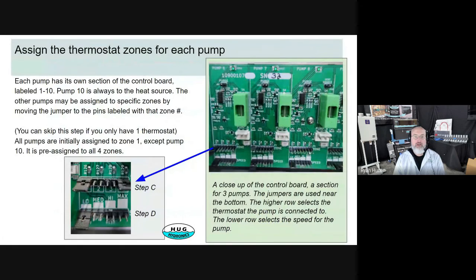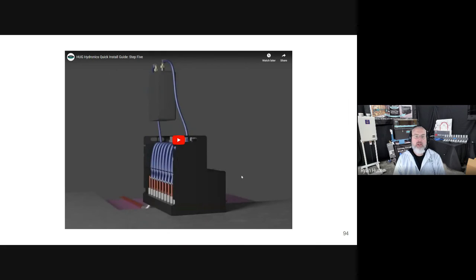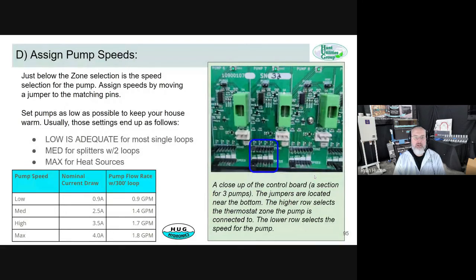All right. So, assign which thermostat controls it and how fast it goes. I've got a pump guide here. That's the table you were looking for. On low speed, it's 0.9 gallons per minute on a single loop. If you ran double loops, it'd be about 0.81 gallons per minute, which is right in the normal range, especially for a concrete floor. For medium, it's 1.4 gallons a minute. It's a pretty big step up. Generally, we only use medium for splitters or 2-loop pump feeding 2 loops, and then it would be about 1.25 gallons per minute.